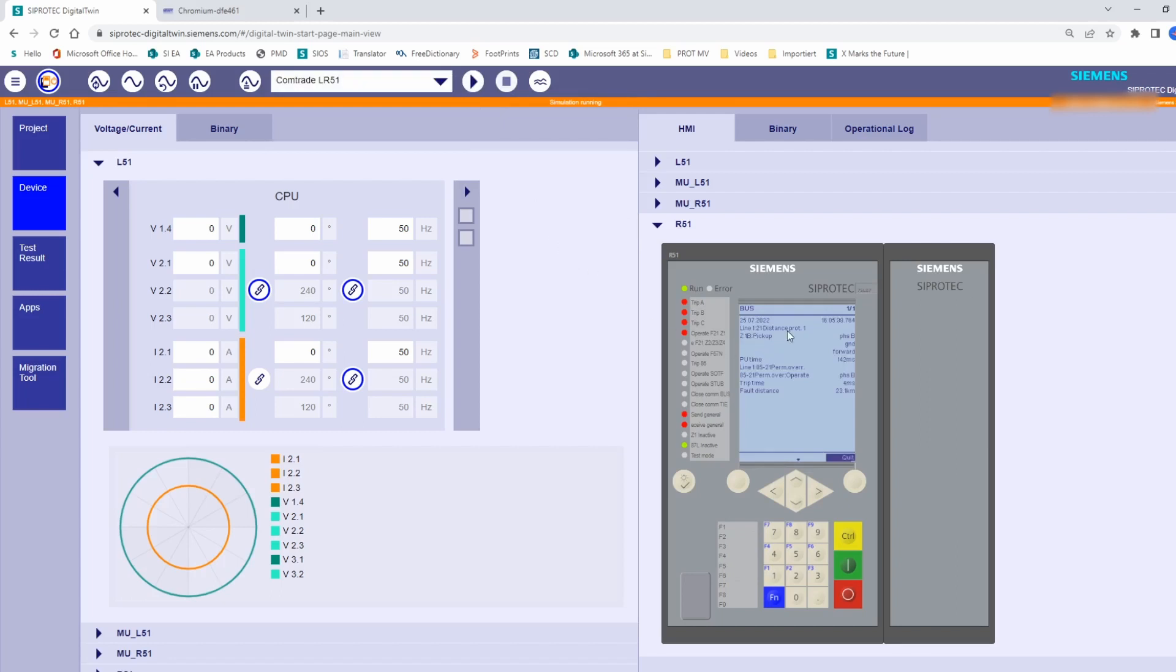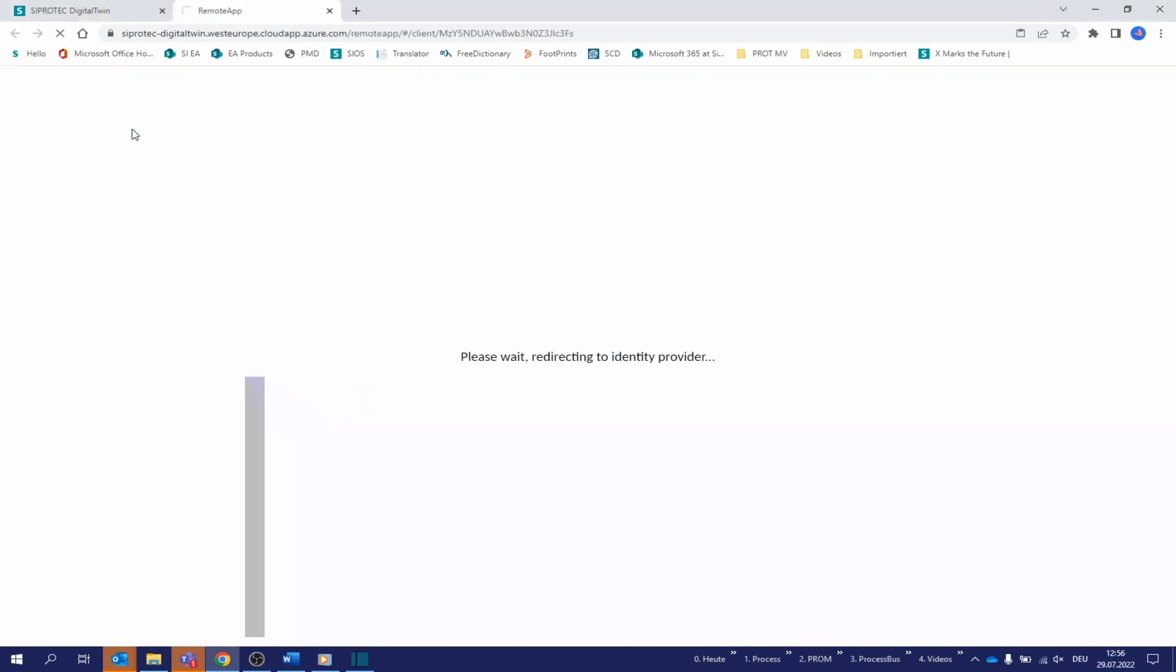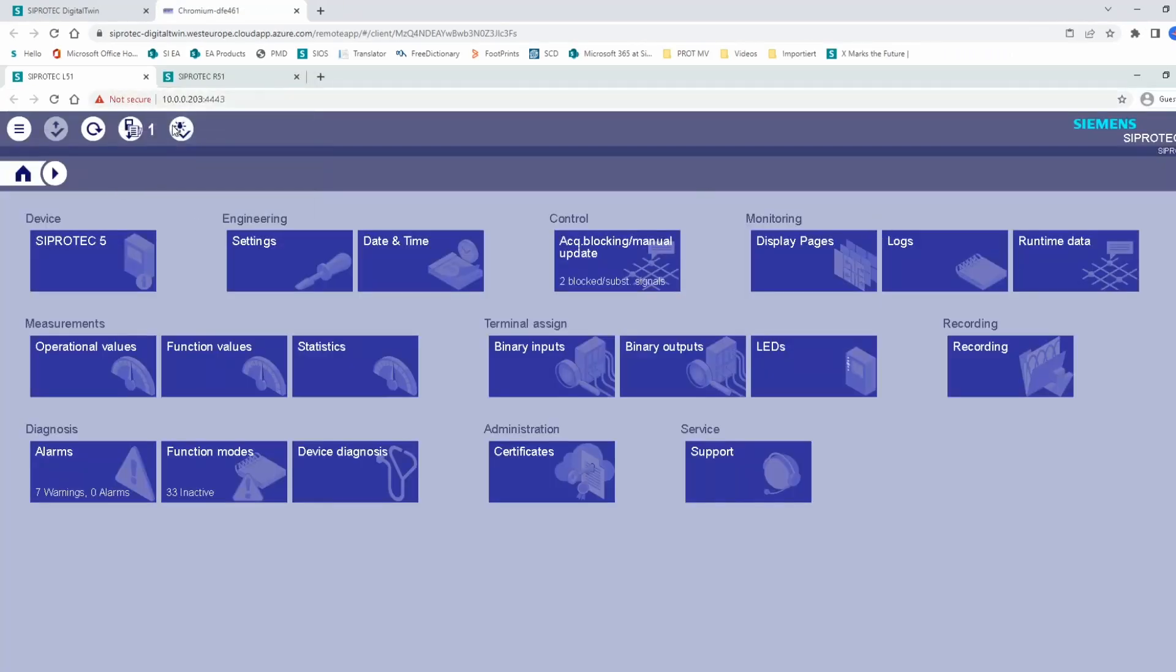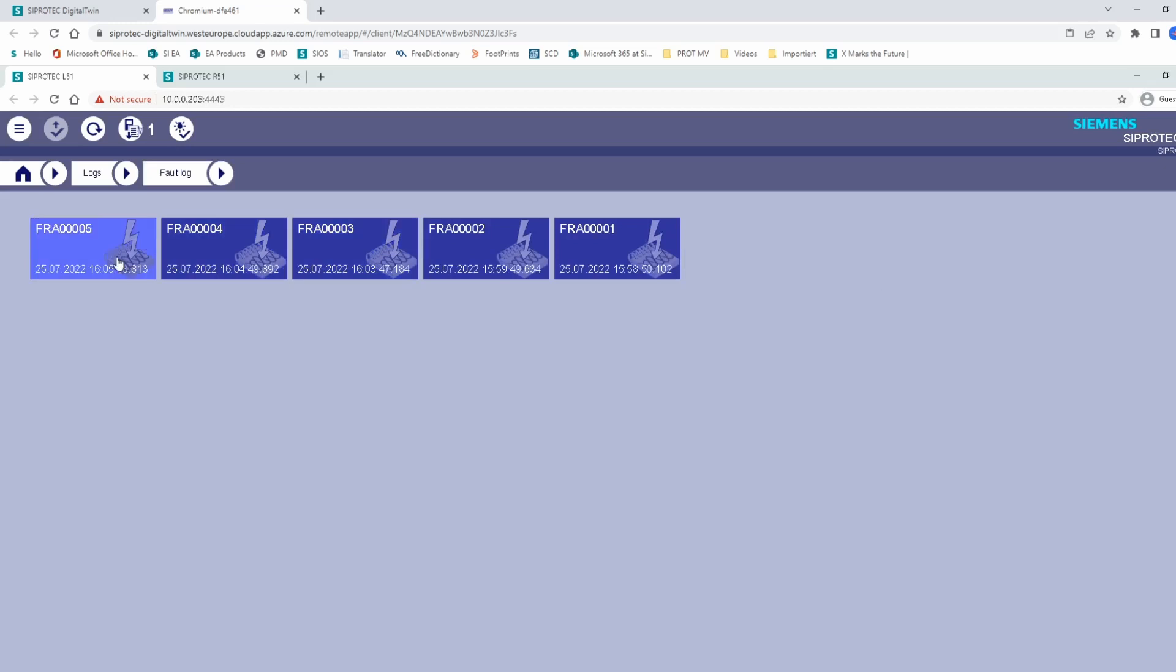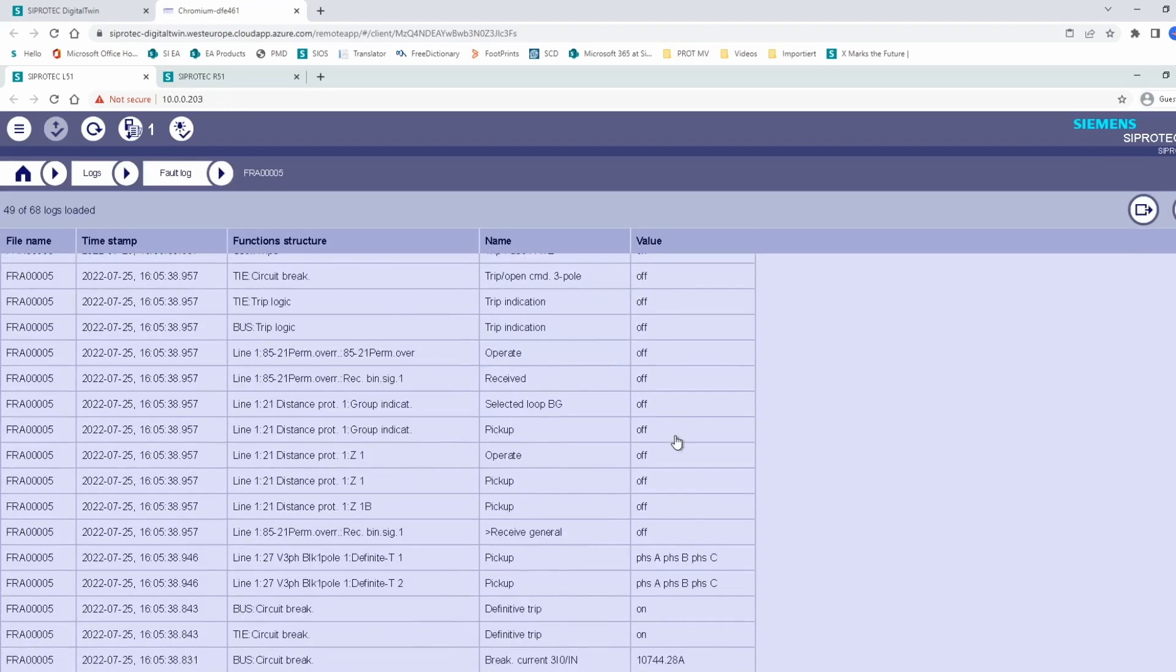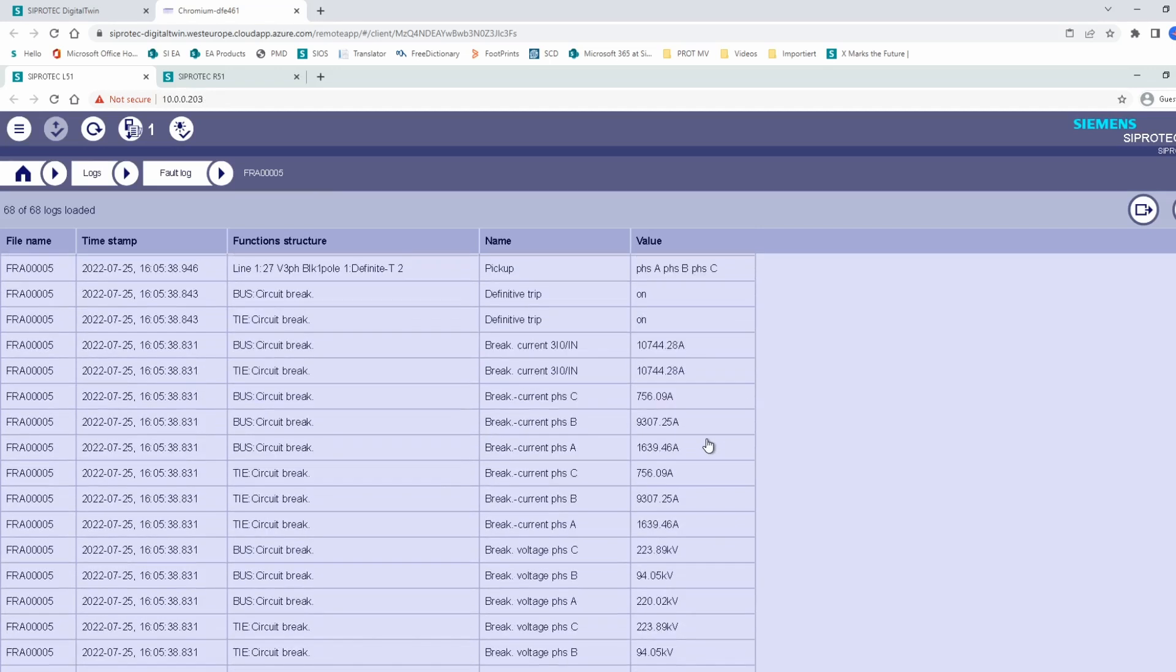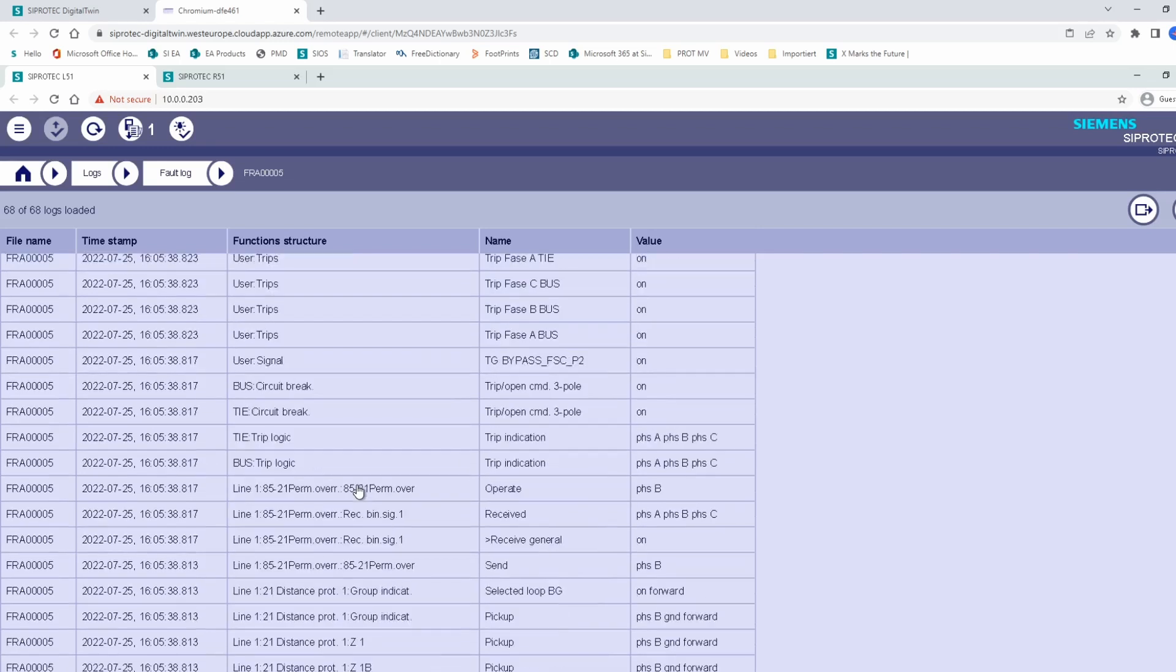Normally we want to analyze each test more in detail. With that in mind, we have included inside the SIPROTEC Digital Twin environment several applications that you can use to improve your testing experience. As an example, you can get access to the web user interface of the devices to read the fault logs and get understanding of the events. It is also possible to download the fault records to be analyzed with the SIGRA online application. And if required, temporary changes can be done in the web interface and permanent changes in the DIGSI 5 application to have the final configuration ready for download.